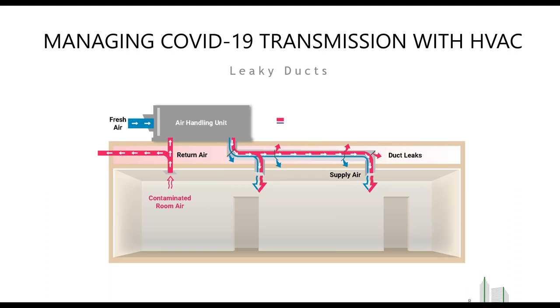So this is the same diagram, but this shows us what happens when you have leaky duct. Basically, all of that fresh air that you're trying to get into the room is leaking out along with some of that contaminated air, and it's not making it into the space. So that dilution that you're trying to have happen in the room isn't happening, because you're not getting what was even designed to begin with, let alone the increased ventilation requirements that they're suggesting now with COVID.